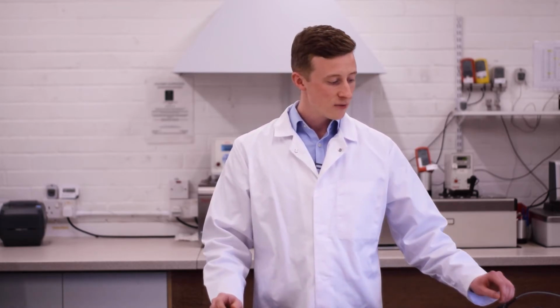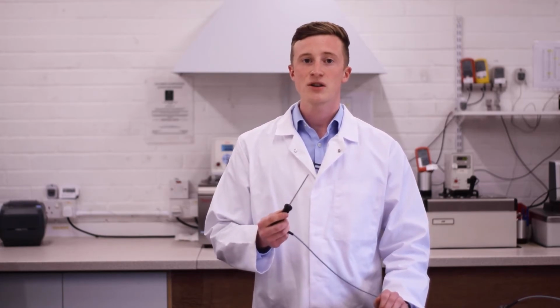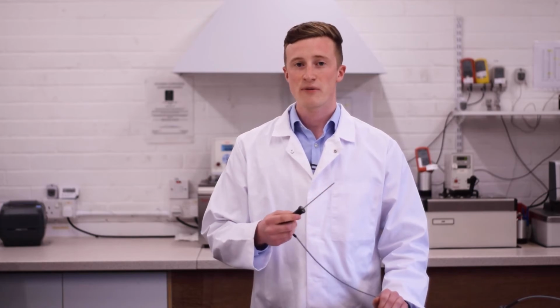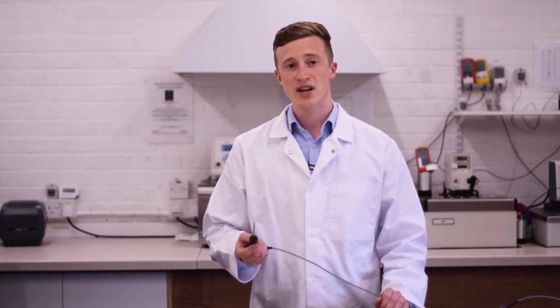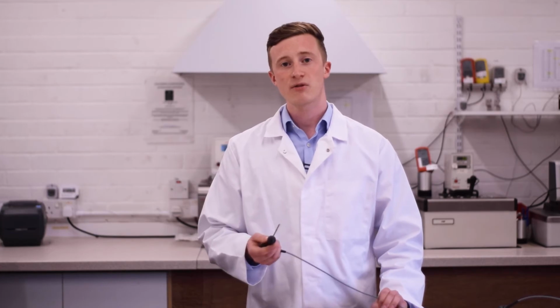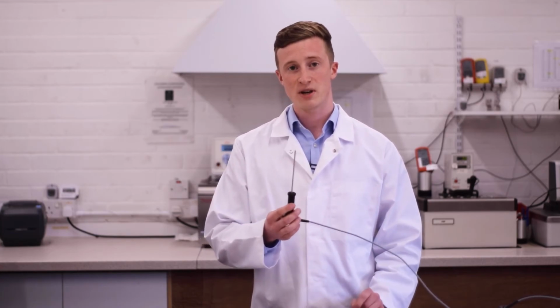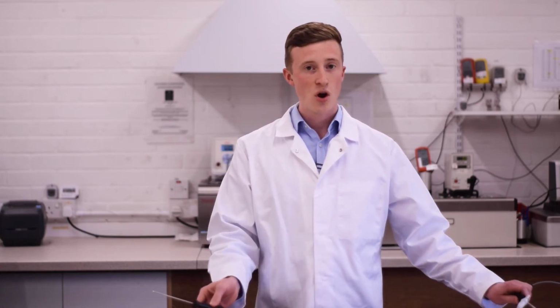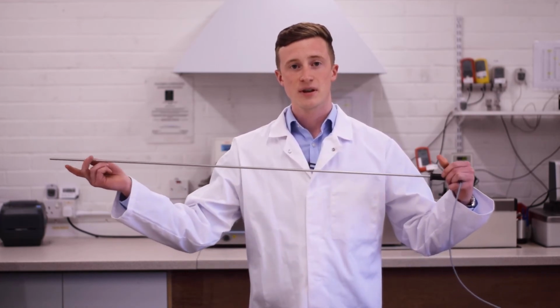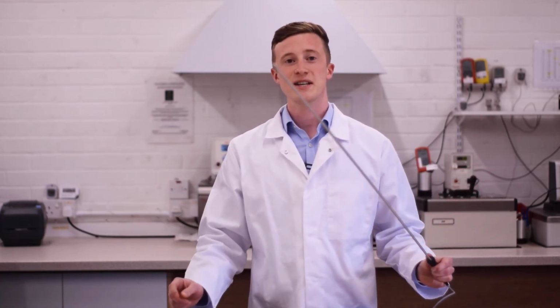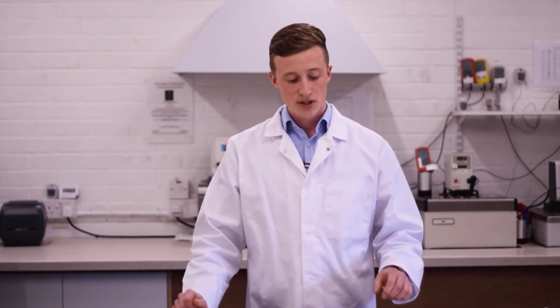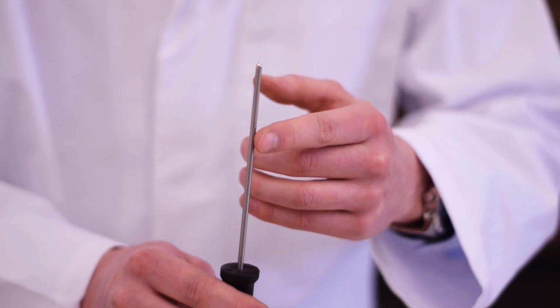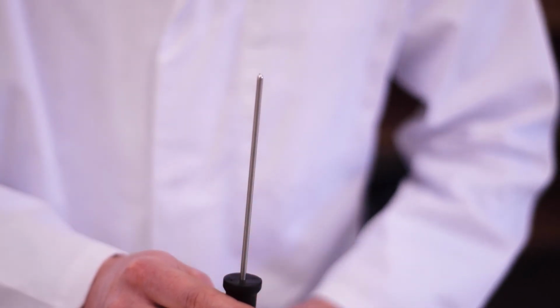Lastly, for measuring liquid temperatures, it is often advisable to use an immersion probe. They are typically used for temperature measurement of products such as beverages, soups, sauces and jams, and are available in a wide range of lengths from 120mm, which I have here, to over a metre. This makes them ideal in deep vats and cooking vessels. As they are being used in liquids, they do not need a penetration point, and this has obvious health and safety advantages.